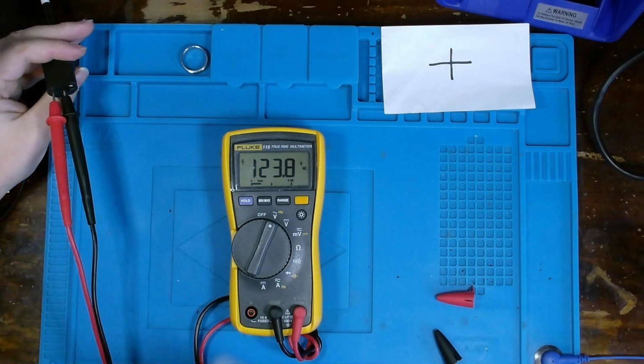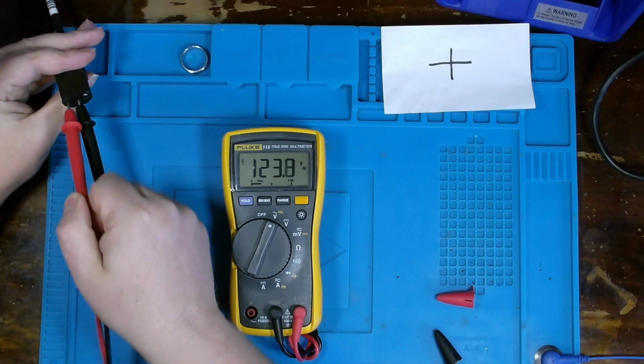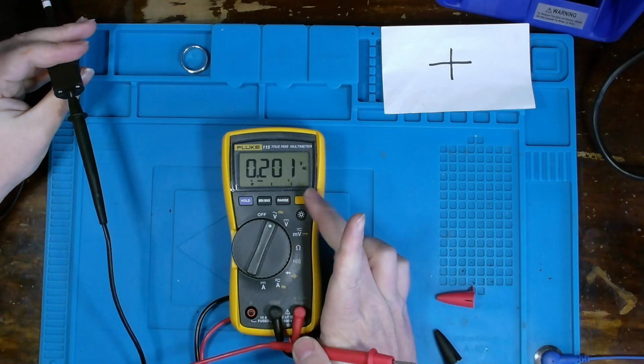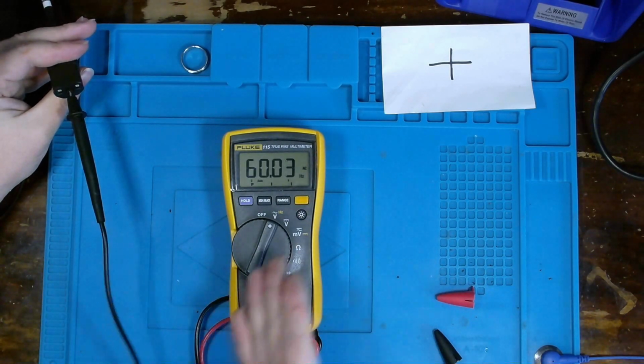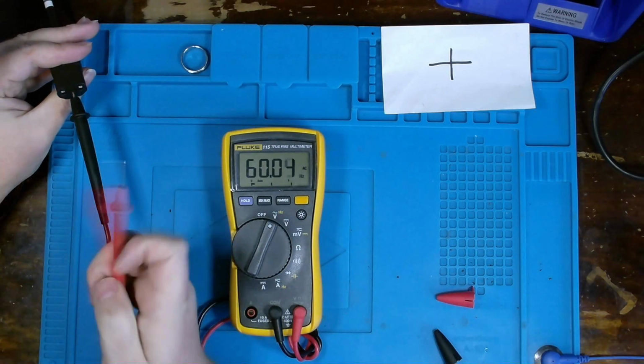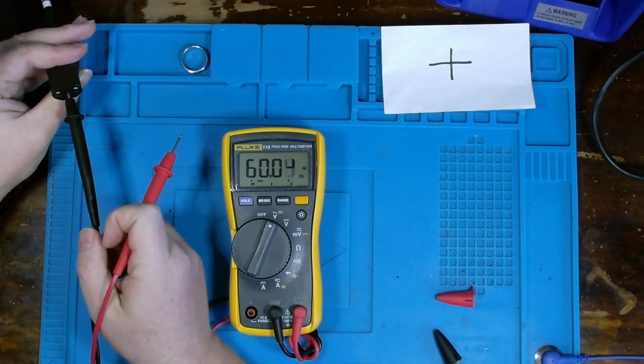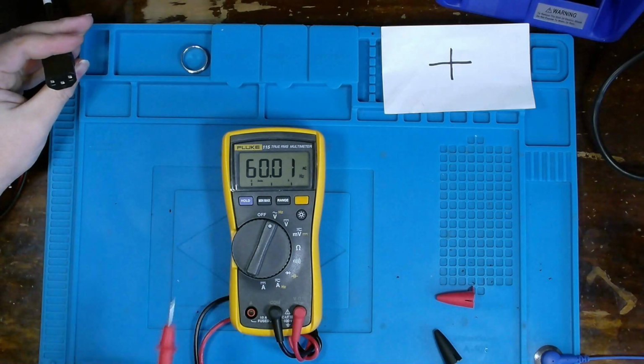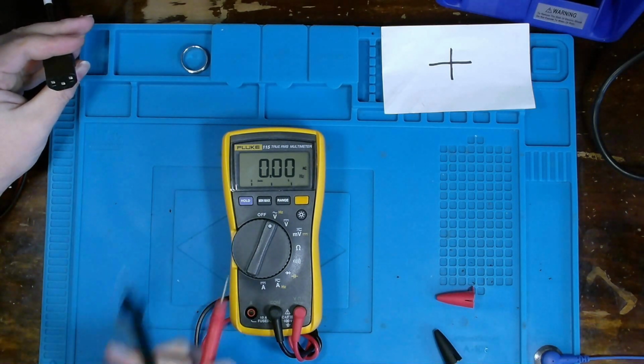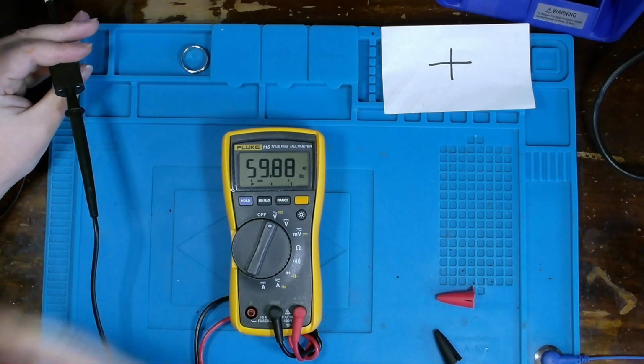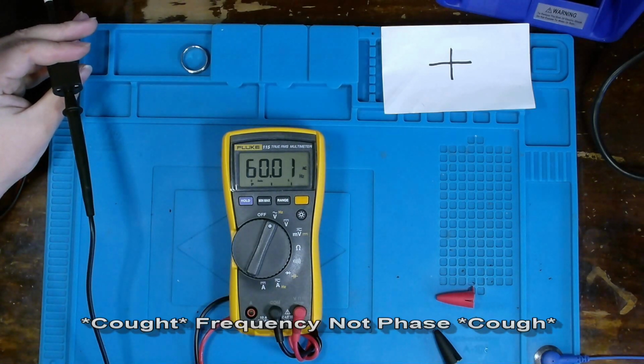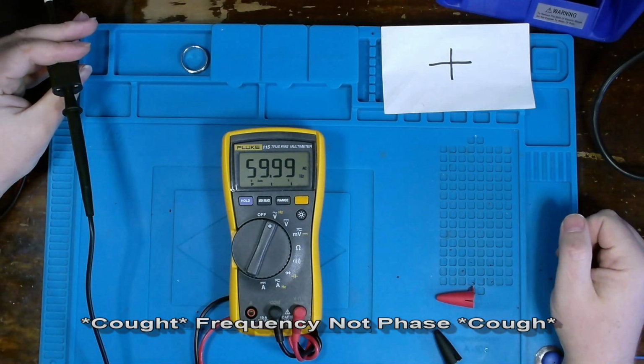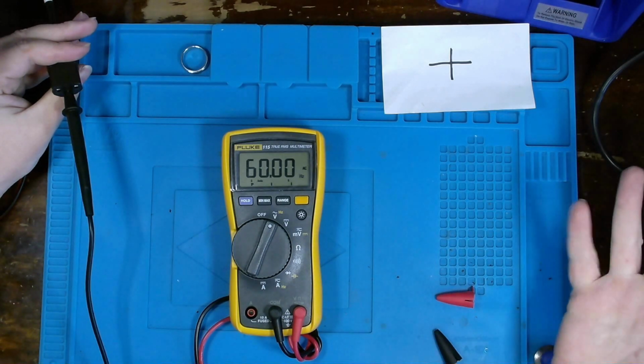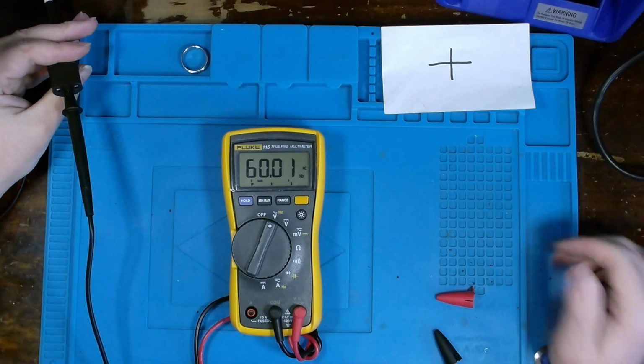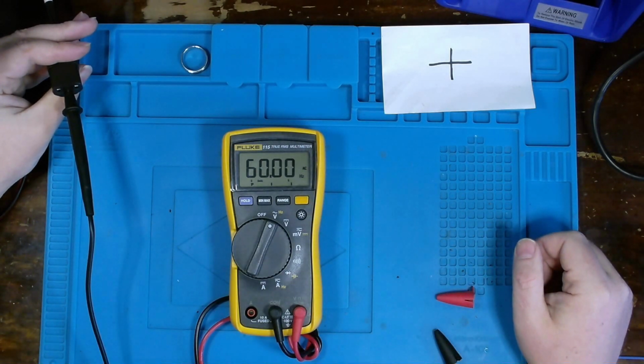Now I'm going to remove this positive lead and switch to this Hertz function. It doesn't take much to make this type of measurement—as a matter of fact, even with my ground probe plugged into ground, because of essentially inductance, I can measure the phase of the AC coming in, and we can see that it is 120 volts AC at 60 Hertz. So that's one good use for this Hertz measurement.